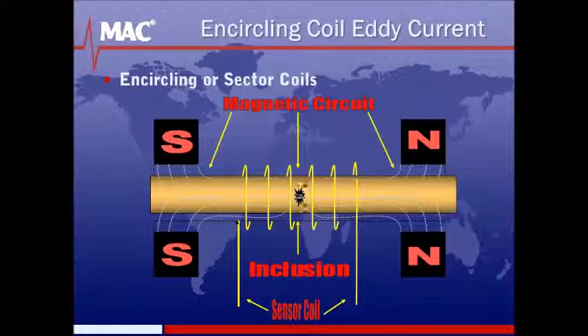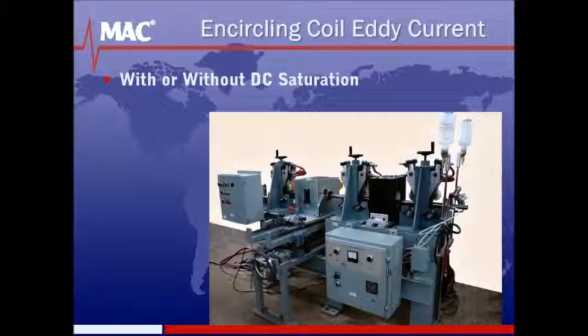Encircling or sector test sensors detect short surface and some subsurface defects on or offline in magnetic and non-magnetic wire, bar, and tube. They are also used to inspect welded tube for short ID or OD defects in the weld zone or on the full circumference. Multimac can operate on a wide variety of non-magnetic products or use direct current saturation systems to inspect magnetic material. A demagnetizer is added to remove residual magnetization.